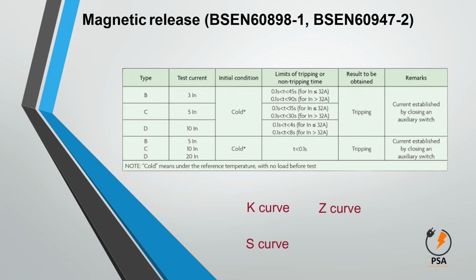Note that the selection of the type of B, C, D circuit breaker should be done very carefully. Wrong selection of CB will create issues in operations. For example, if a B-type CB is put in for a C-type CB application, then the Type B MCB will trip again and again on surge or temporary fault, which is not required for the system. In the same way, if a Type C CB is put in for Type B, then Type C will not trip on fault and equipment will be burnt.